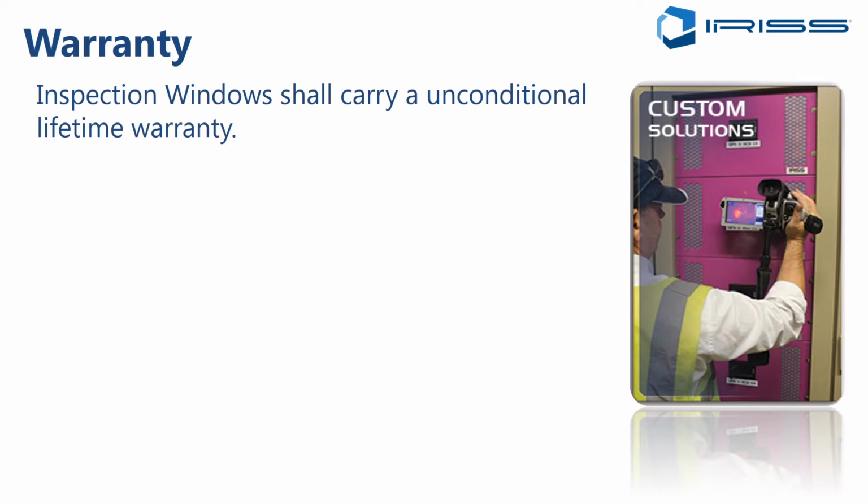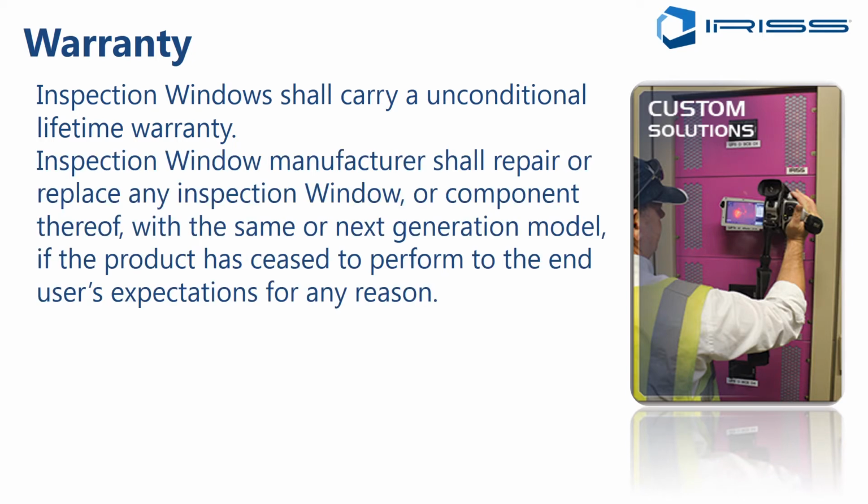Finally, warranty. You can specify your warranty conditions, and there are windows available from IRISS and I think from others that carry an unconditional lifetime warranty. So an inspection window manufacturer should be able to repair or replace any inspection window or component with the same or a future generation model if the product has ceased to perform to the end user's expectations for any reason. That's truly an unconditional warranty statement, and that's the statement that we recommend you embed in your specification.